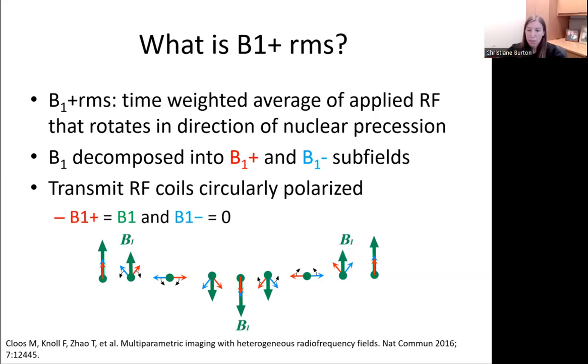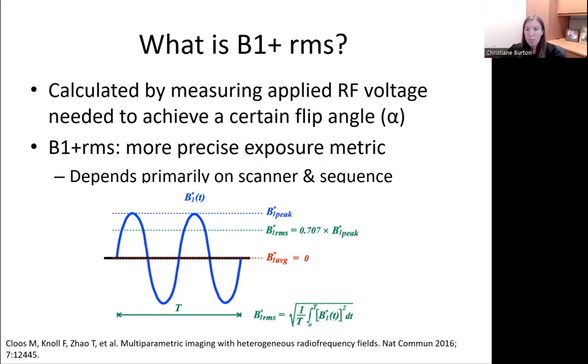The example below shows a linearly polarized B1 demonstrating equal and opposite B1+ and B1- components. In the modern era, nearly all transmit RF coils are circularly polarized, meaning ideally that B1+ is equal to B1 and B1- is equal to 0. The image is showing decomposition of an oscillating RF field, B1 green, and B1+ red and B1- blue subcomponents. The term B1+ RMS refers to the root mean squared value of B1+ averaged over a period of 10 seconds. B1+ peak values may also be used.